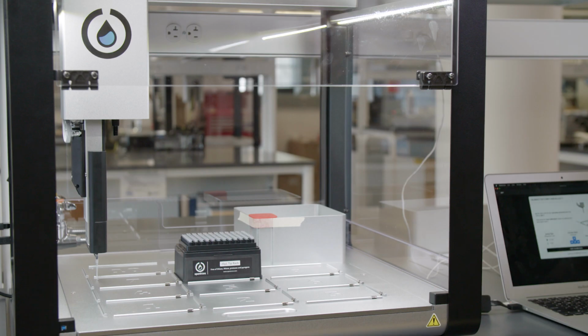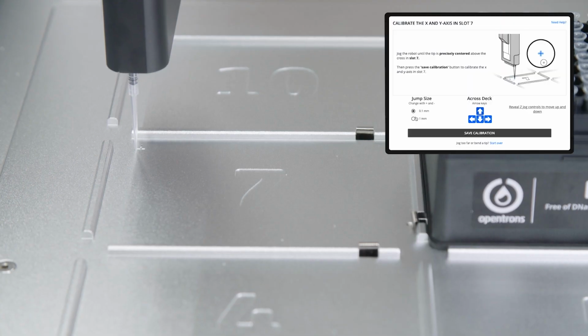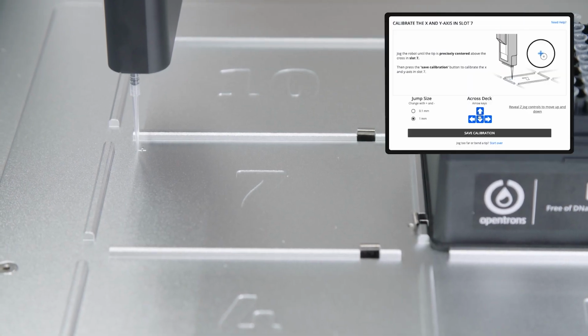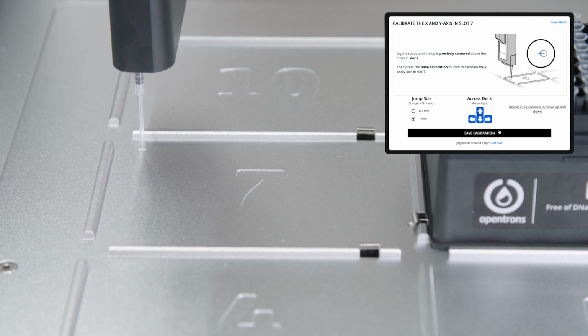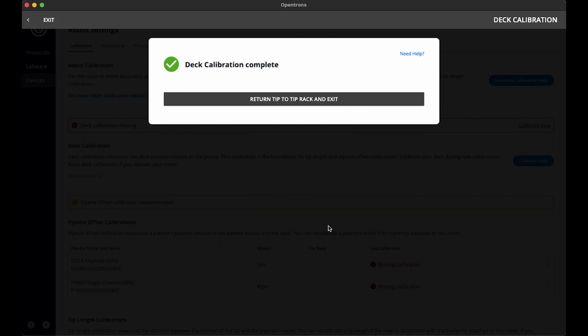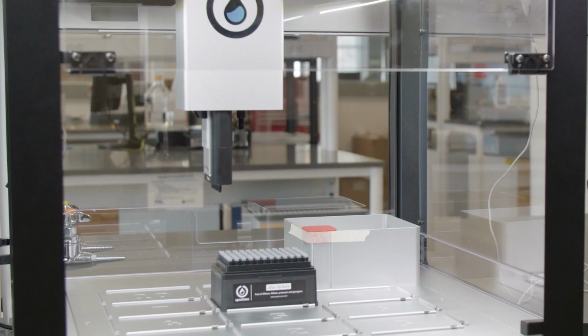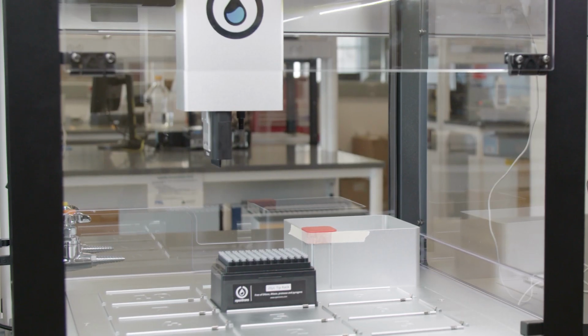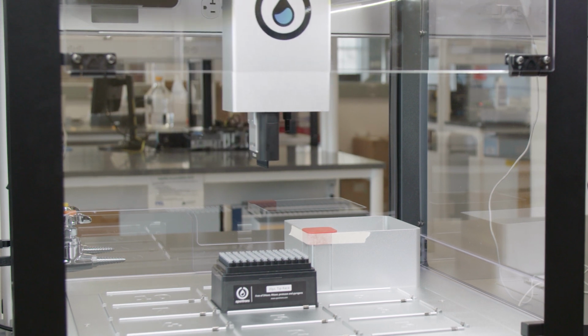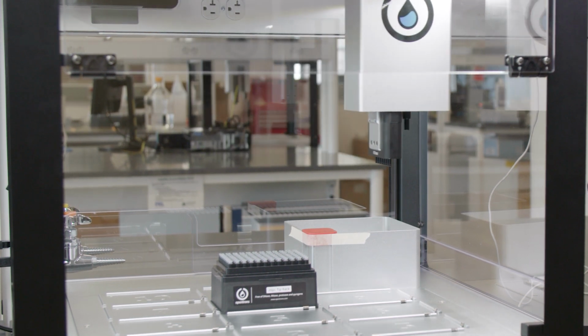Just like the last steps, I need to jog the pipette so the tip is precisely centered in the cross. The tip is precisely centered in the cross in slot 7. I will save this calibration. A check mark will appear letting me know that the deck calibration is now complete. So I will click return tip to the tip rack and exit, and the robot will now home.